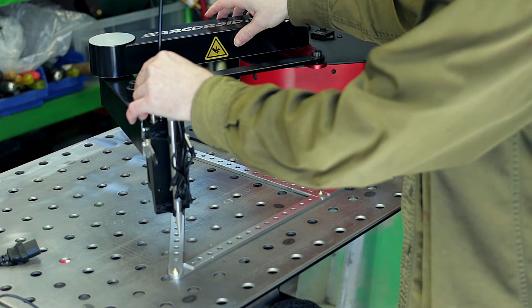Something I'd like to cover about calibration: make sure you clamp your machine down. I'm using a fixture table here, so I put a clamp on this side. Be careful about putting one on the other side, because when it goes to do its home, you could end up hitting it. So you need either a low profile clamp or something that's not going to get in the way of that arm homing.